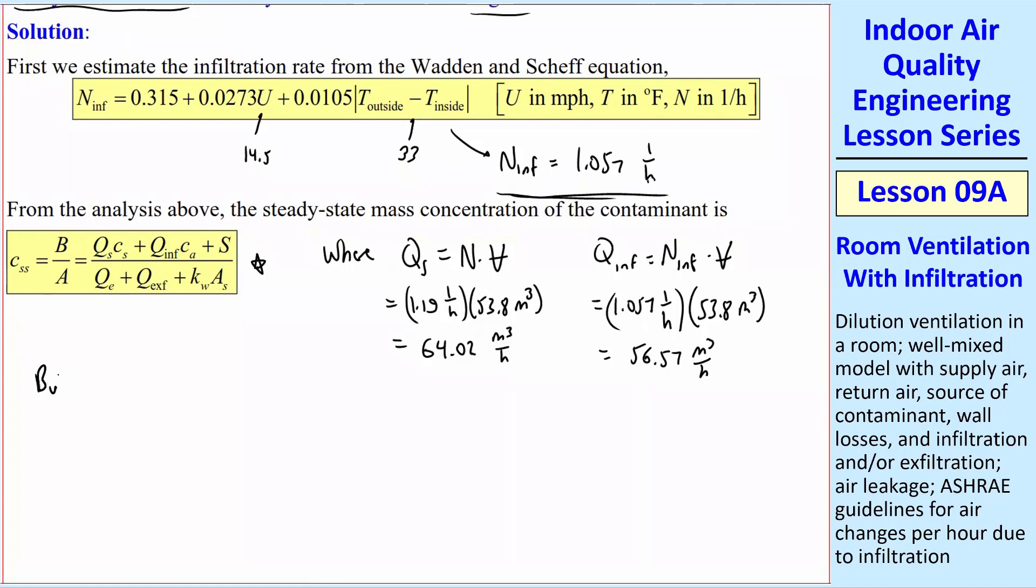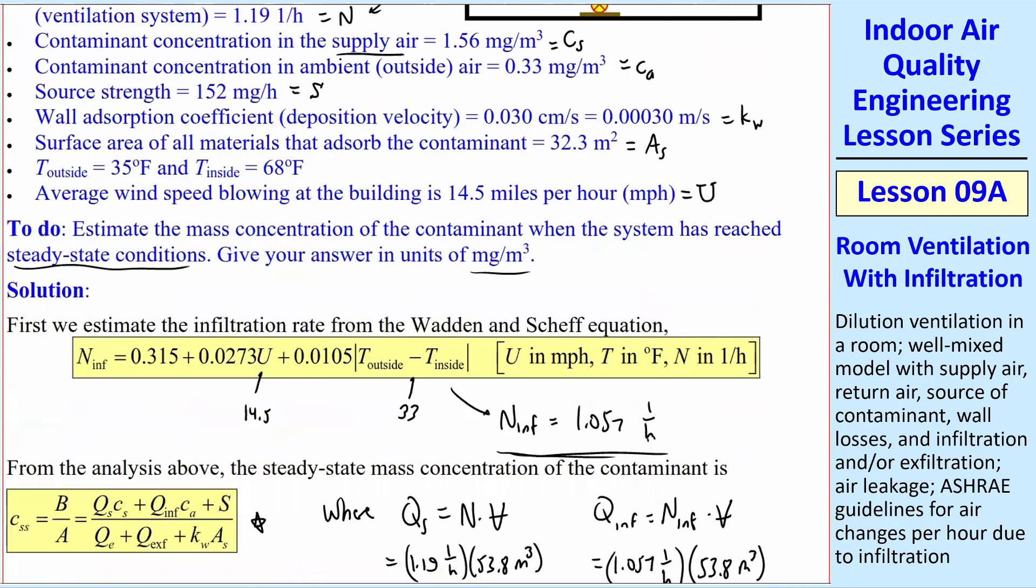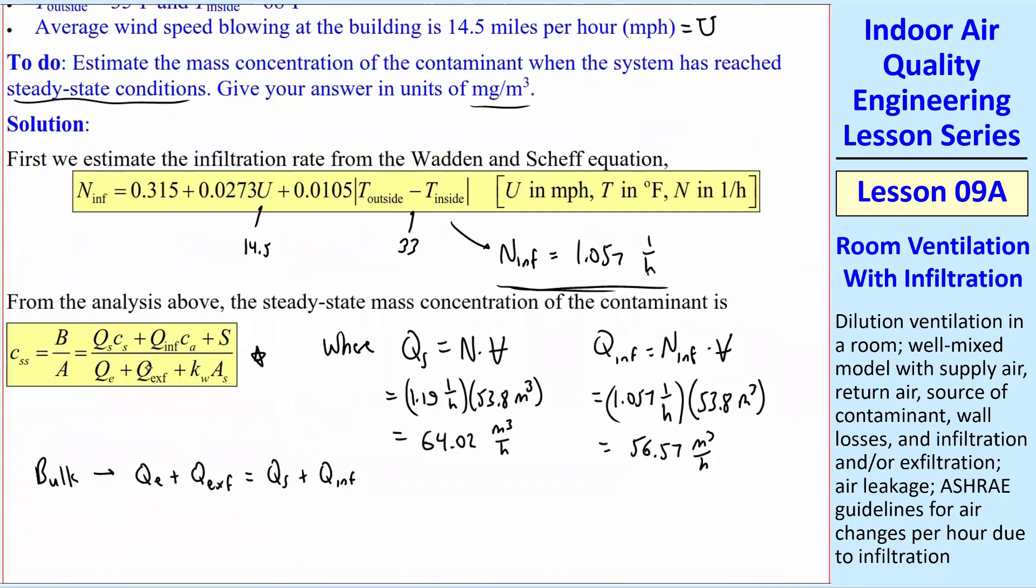And we also have the bulk air: Q_E plus Q_EXF is equal to Q_S plus Q_INF. I don't really care how the split is between Q_E and Q_EXF. I don't care how much goes out this exit and how much goes out this exit since they both have the same C. All I care about is the total Q_E plus Q_EXF. And that appears together in this denominator. So we're going to let that equal Q_S plus Q_INF. We have Q_S and we have Q_INF.